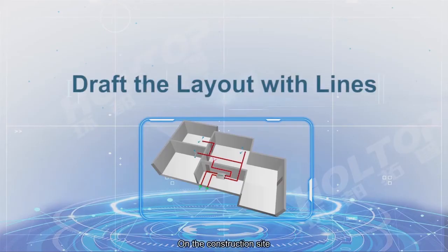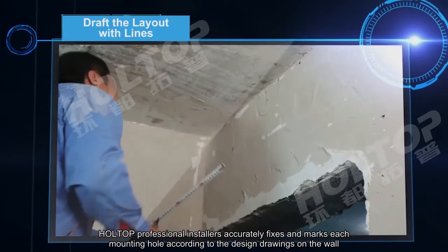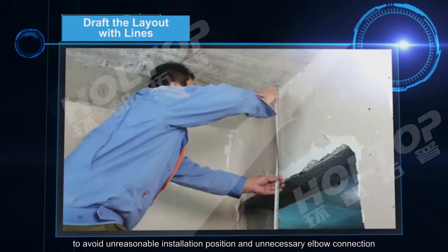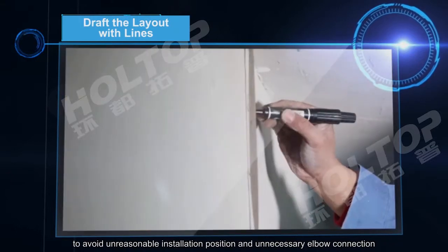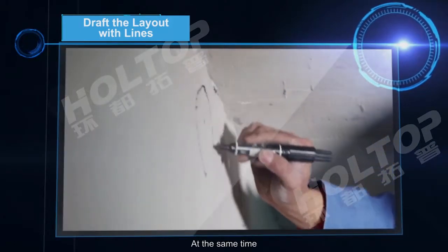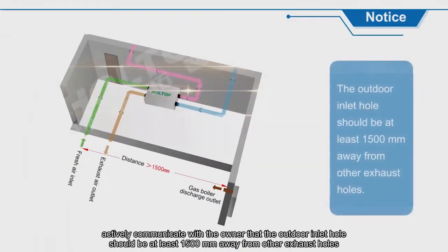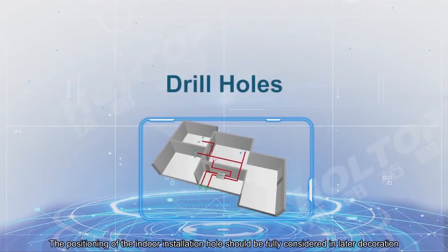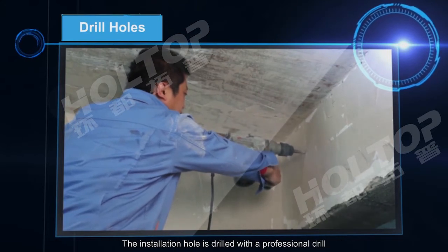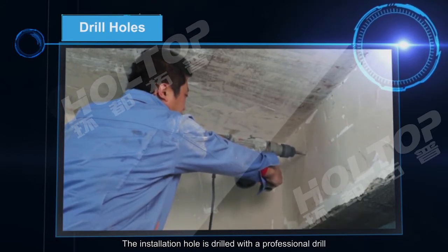On the construction site, Holtop professional installers accurately fix and mark each mounting hole according to the design drawings on the wall, to avoid unreasonable installation positions and unnecessary elbow connections. At the same time, they actively communicate with the owner that the outdoor inlet hole should be at least 1500mm away from other exhaust holes. The positioning of the indoor installation hole should be fully considered in later decoration, and the installation hole is drilled with a professional drill.